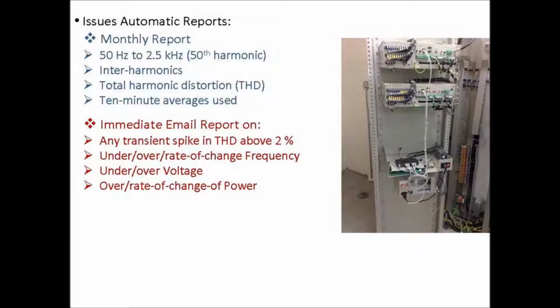We get reports every month that tell us what's going on, all the way up to the 50th harmonic, plus some interharmonics. So in between the second and third, there are lots and lots of non-integer values that you can have harmonics at, and the THD, and obviously 10-minute averages. And if there's an event on the system where you've got a spike above 2%, which is when you're starting to get into danger territory, or any other strange behaviour, you get an immediate report from these power quality recorders.